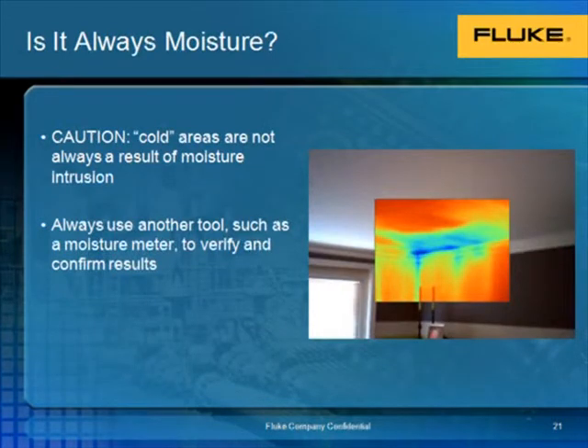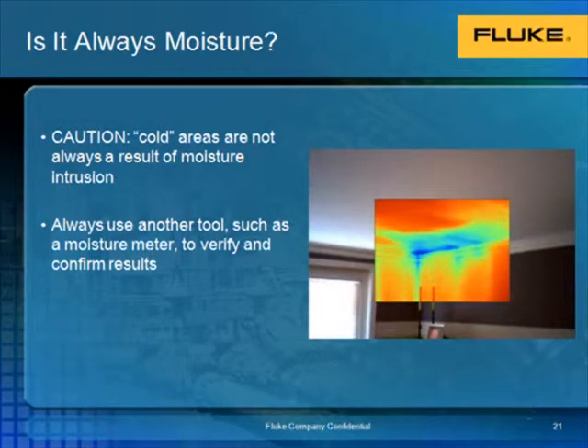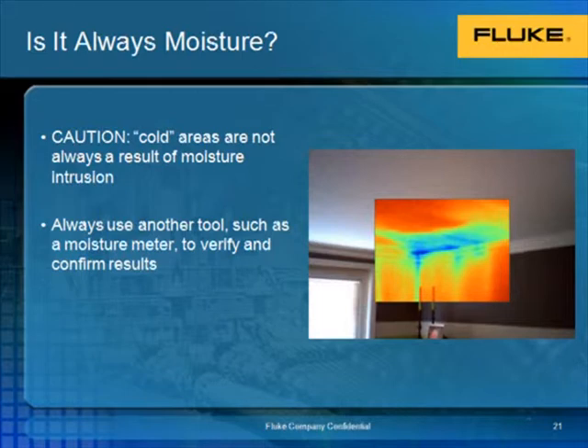Since moisture has been the focus of the past few slides, I'd like to caution everyone that areas showing up cold on a thermal imager are not always the result of moisture intrusion. As you see in this picture, we're actually looking at an insulation gap. It also shows up cold, but that is because the outside temperature is so much colder than the inside temperature. It's always a good idea to utilize another tool such as a moisture meter to verify and confirm your findings.